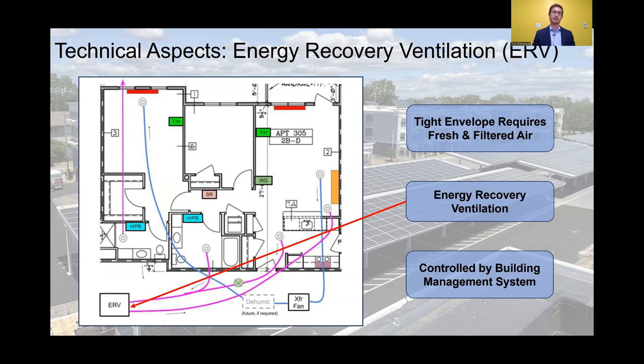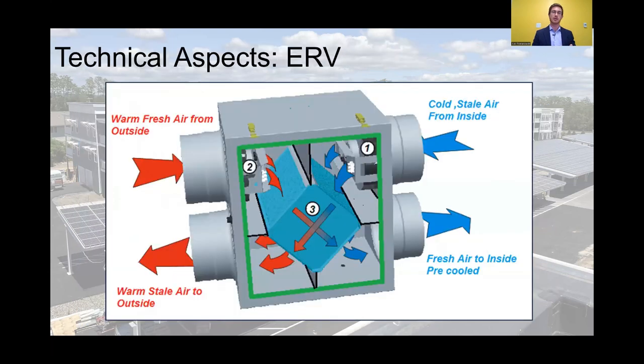They've got an energy recovery ventilation system. When the envelope is as tight as Solara's, you're not going to have outside air exchange because the building's not breathing. This means that you need to bring in fresh and filtered air through an energy recovery ventilation system. This is controlled by the building management system, and it works by bringing in unconditioned air, and then conditioned stale air is going to travel through, and they don't mix, but they do exchange heat and moisture. And that means that your fresh and filtered air is going to be coming into the apartment closer to the temperature of your conditioned air, so you don't have to spend as much energy cooling that down.